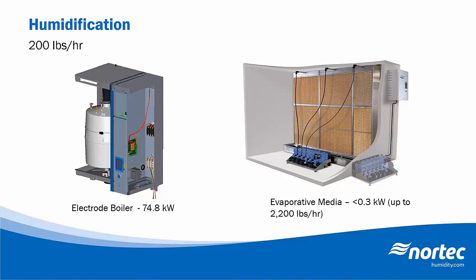So if we were to compare the energy consumption for, let's say, a 200-pound an hour humidification load, an electrode style boiler would require about 75 kilowatts of electricity, whereas an evaporative media system could provide that capacity using less than about 0.3 kilowatts of electricity. So you can see right off the bat that if we need humidification as well, looking at an evaporative media system or an adiabatic system can save quite a lot of energy just on that side alone. But it is important to keep in mind that with an adiabatic system, the cooling effect and humidity go hand in hand. So as we increase the cooling from an evaporative system, the humidity level also increases. So you just need to keep that in mind to ensure that the moisture content of the air doesn't rise above the recommended or the allowable range.